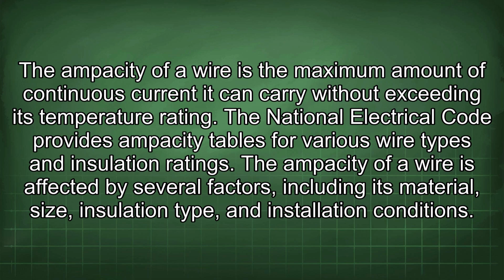The ampacity of a wire is the maximum amount of continuous current it can carry without exceeding its temperature rating. The National Electrical Code provides ampacity tables for various wire types and insulation ratings. The ampacity of a wire is affected by several factors, including its material, size, insulation type, and installation conditions.